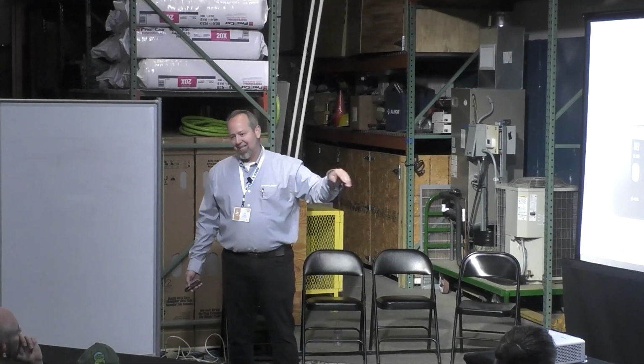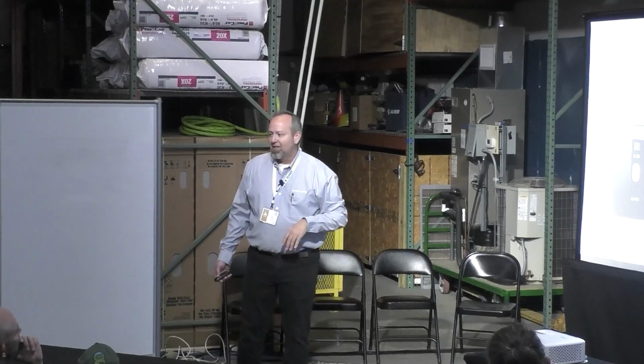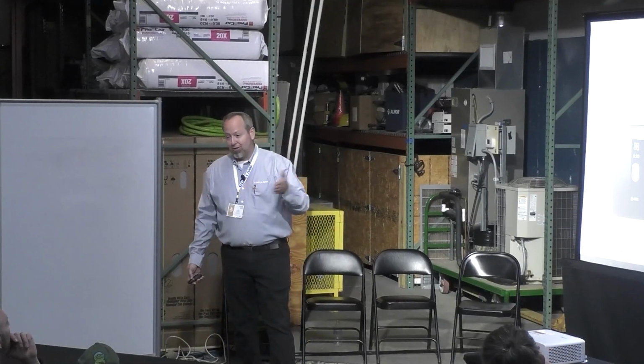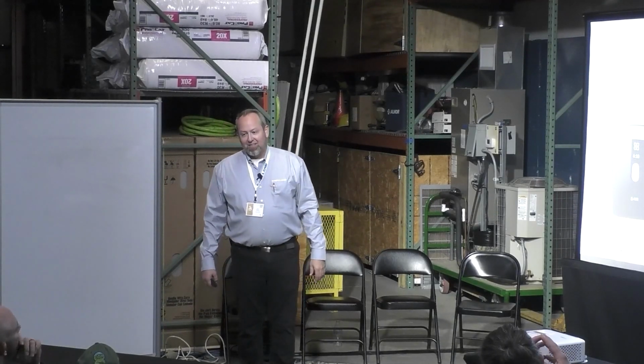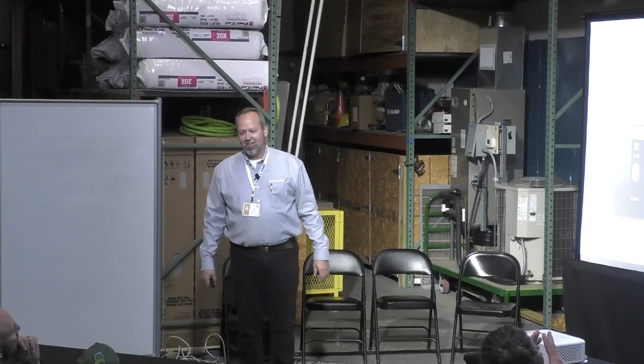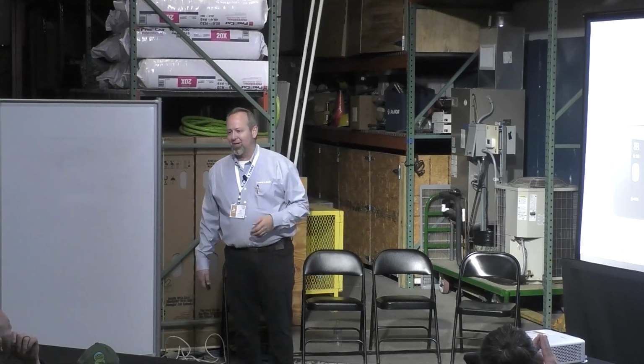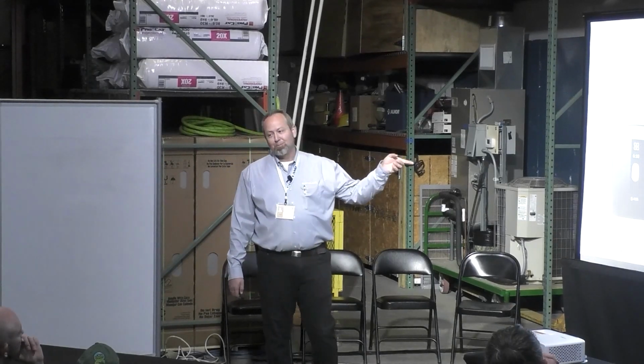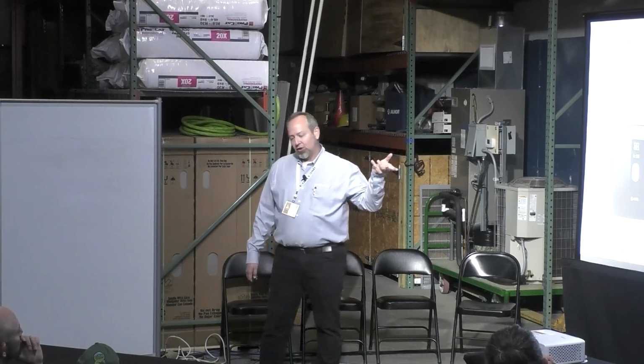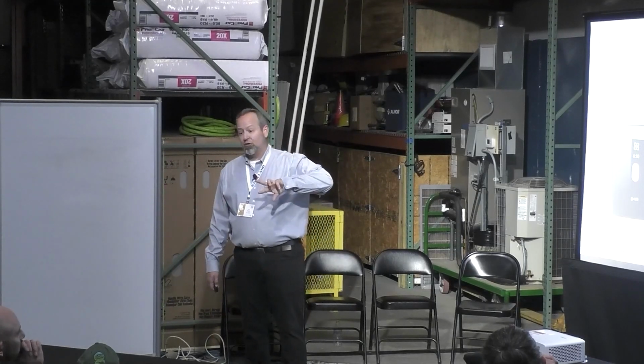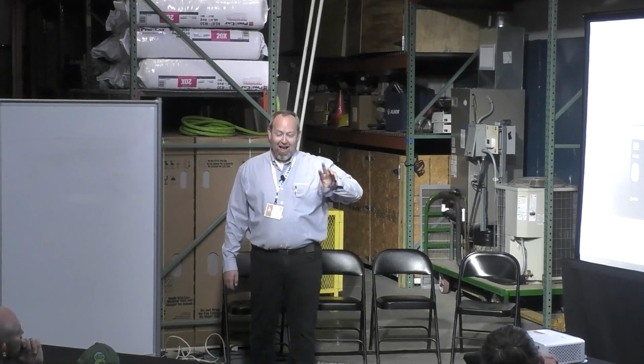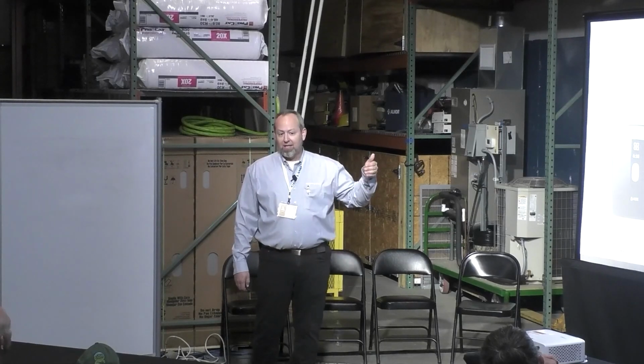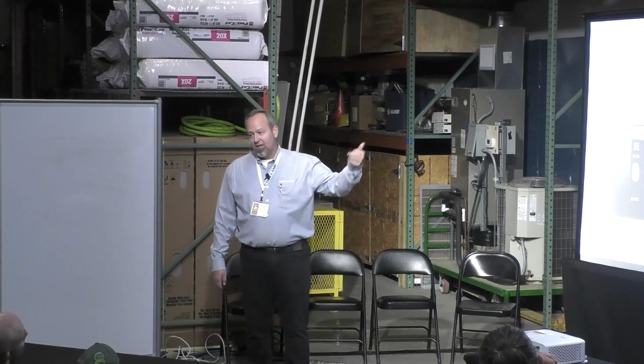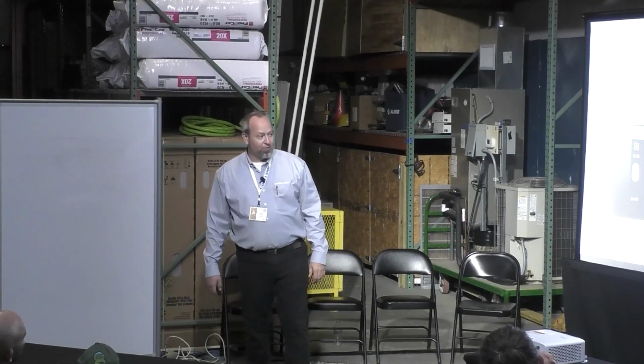It's factory default so that it won't kick out on a balance point. You have to push it down to somewhere between 40 to 30, or wherever you want that balance point to be. So it's designed so that the homeowner doesn't say, wait a minute, something's not on and it should be. But that feature is built in, where the thermostat actually switches and makes the second stage or the second fuel the primary fuel anything below the temperature that's being read by open weather.